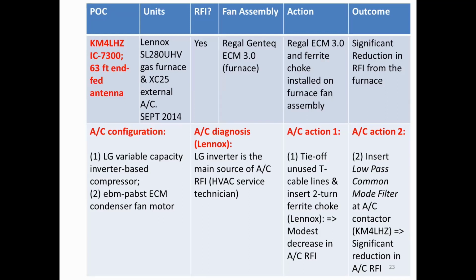The AC configuration has an LG variable capacity inverter-based compressor, that's a mouthful, and an ebm-pabst ECM condenser fan motor. When the service techs were diagnosing my problems, because they came out under terms of the warranty and examined my system and isolated the source of the RFI, they said there were no problems at all with the condenser fan motor, but they told me I definitely had an inverter problem. And I had no idea what they were talking about. I was ready to reach for Google Translate by the end of that conversation. But I found out what an inverter is. And it converts, as I said, single phase AC to triple phase variable frequency AC to drive a variable frequency compressor motor.